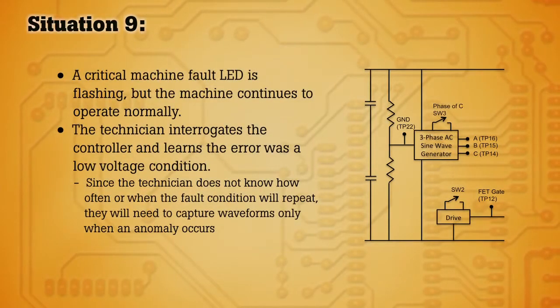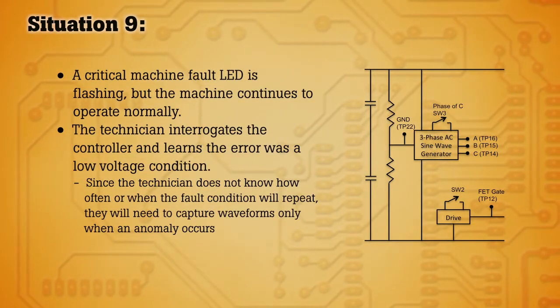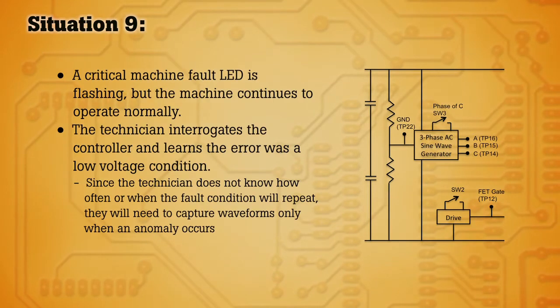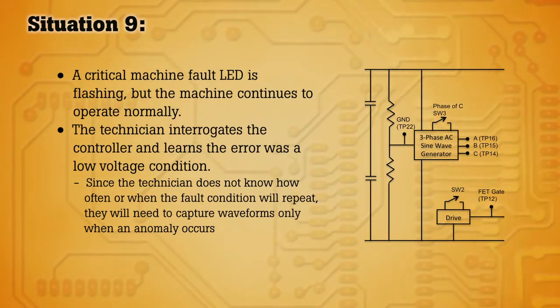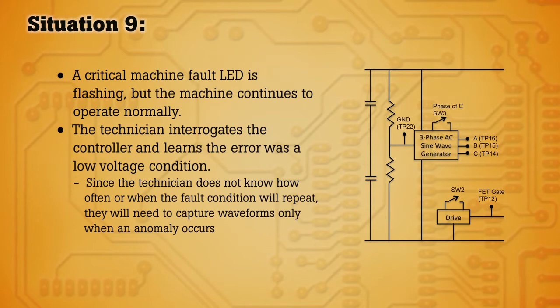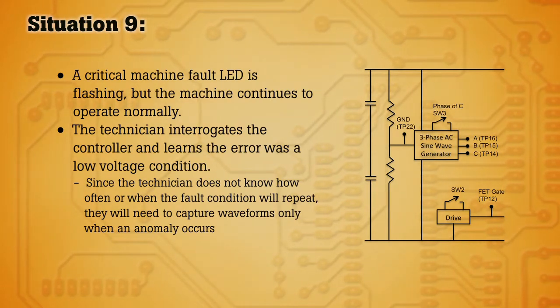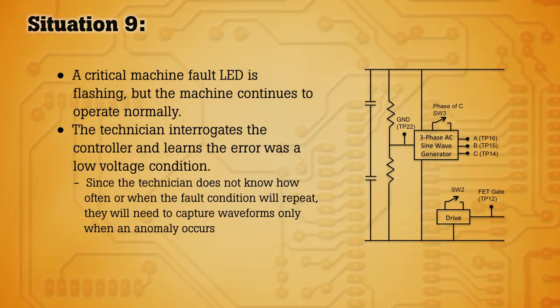Here we have a scenario where you have a critical machine with a fault LED flashing, but the machine is continuing to operate normally. Diagnosing the controller you find the error codes indicate there has been a low voltage condition. Since you don't know when the fault occurred or how often it's happened, it's difficult to diagnose the root of the problem.